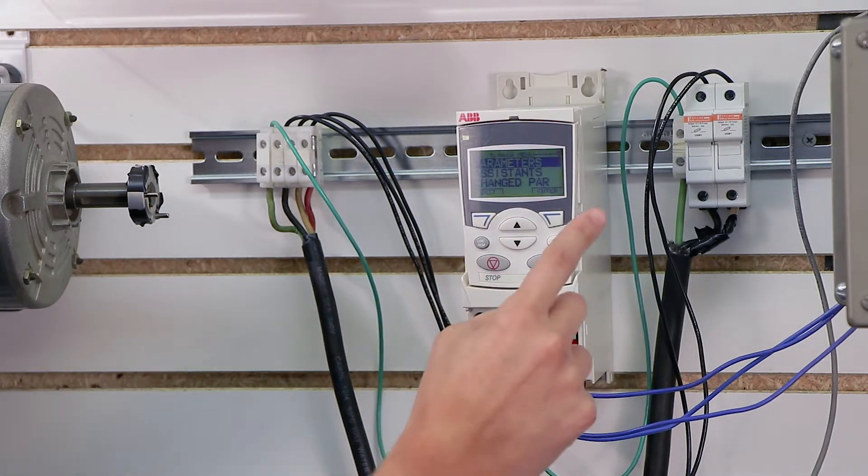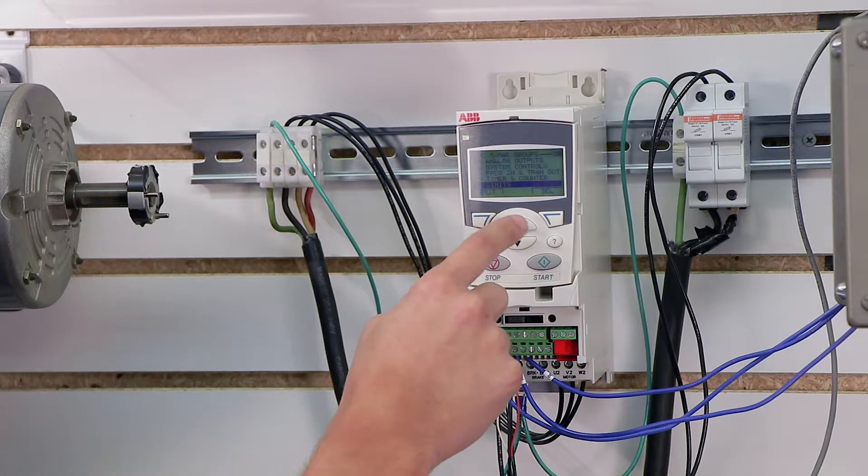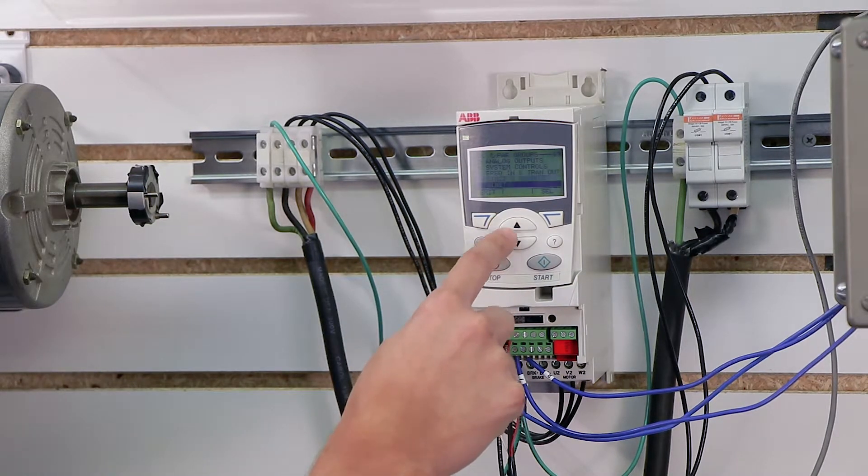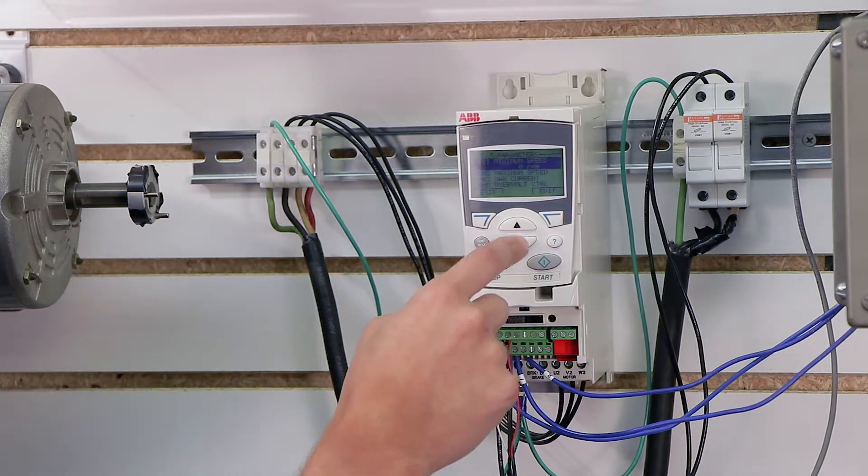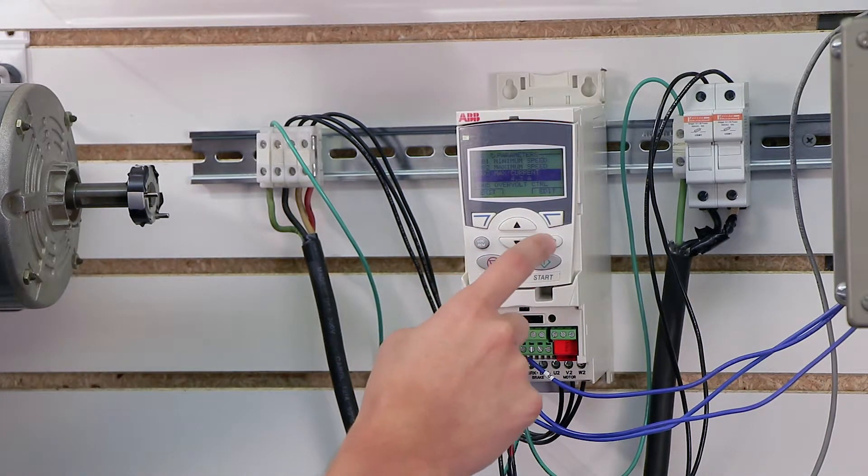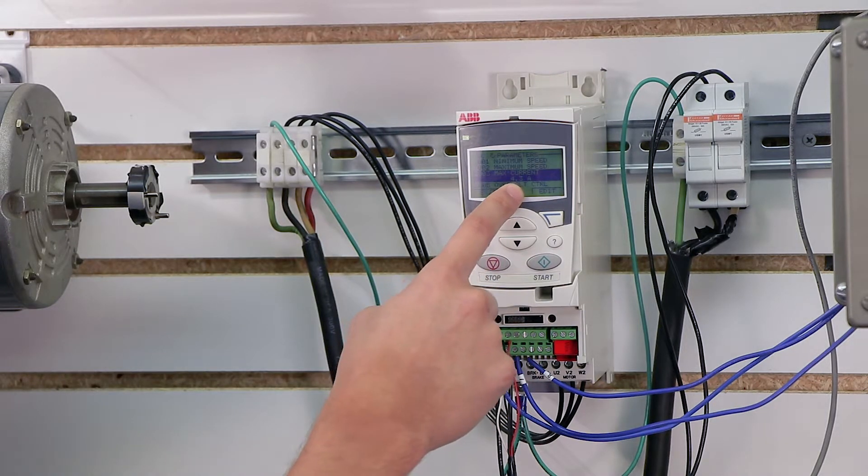Now, to do that, just press Menu and make sure it's on Parameters and click Enter. And then we go down to our Limits section, which is Parameter Group 20. We click Select. We scroll down to Max Current. And as you can see on my drive, it says 4.3 amps, which is a lot of current because I have a 2.4 amp motor.